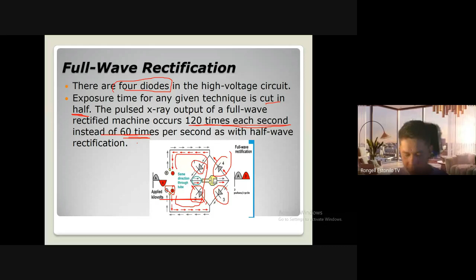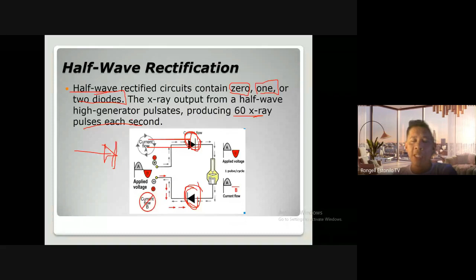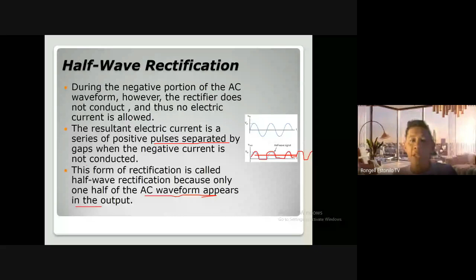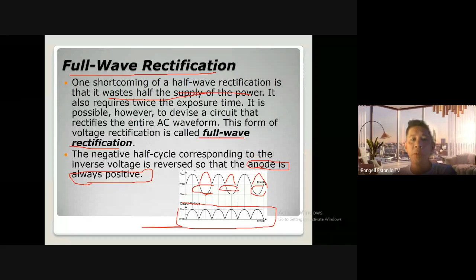Okay. Next, we have the single-phase power generator bank. Again, this is different because these are the processes of rectification. There are only two things we have to take note of: either it undergoes half-wave rectification or full-wave rectification. But again, most manufacturers prefer full-wave rectification. These are the types of generators used in an X-ray facility. It depends on the machine. I'm not saying all are single phase, all 3-phase 6 pulse, 3-phase 12 pulse, or all high frequency. It depends on the capability or on the supply.